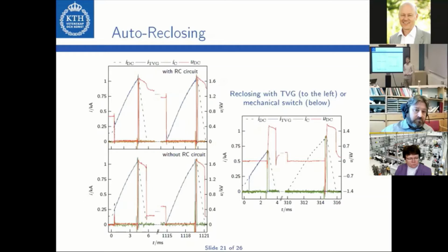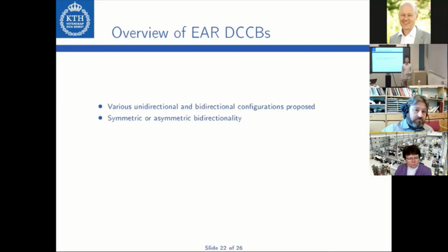The advantage of using an arcing mechanical switch is that it provides redundancy. In case there is some problem with the triggered vacuum gap, it is still possible to operate the enhanced active resonance circuit breaker similar to a conventional current injection circuit breaker. Now let's have an overview of the EAR DCCBs. We have proposed various configurations of the EAR DCCBs, both the unidirectional and bidirectional configurations. We have proposed symmetric and asymmetric bidirectional configuration. Asymmetric means that the interruption capability of the configuration is not the same in both current directions. This can considerably reduce the component count and hence also the costs.